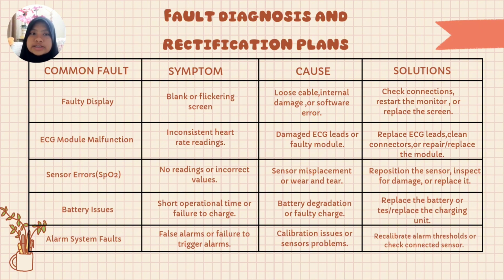After that, ECG module malfunction. The symptom is inconsistent heart rate reading. It is caused by damaged ECG leads or faulty module. The solution is to replace ECG leads, clean connector, or repair or replace the module.